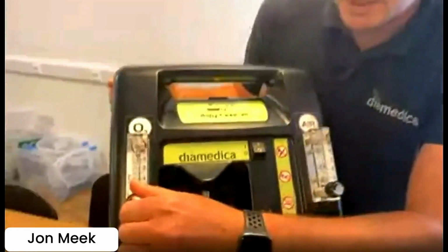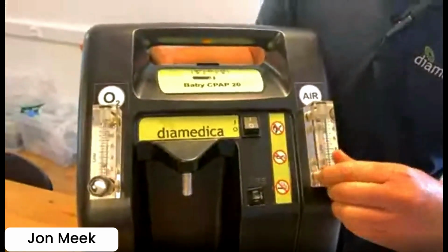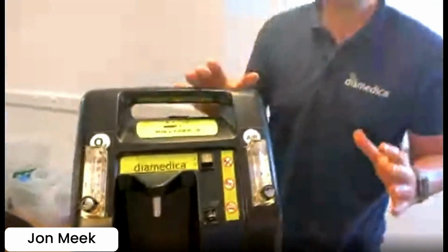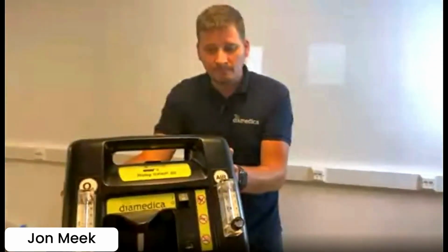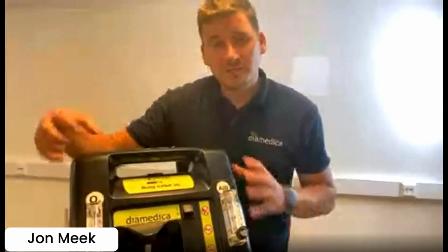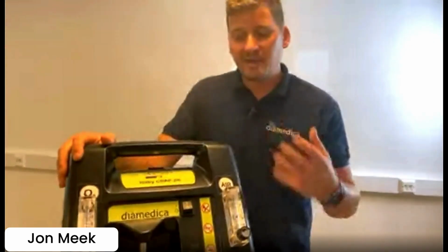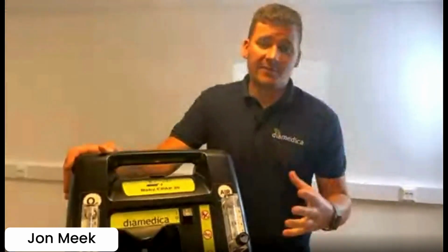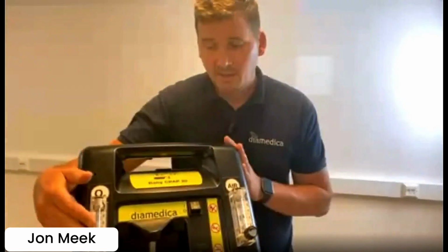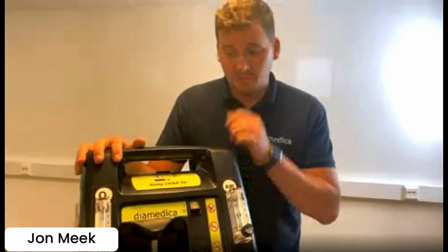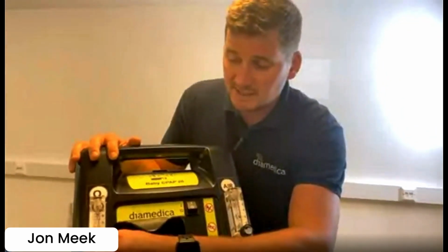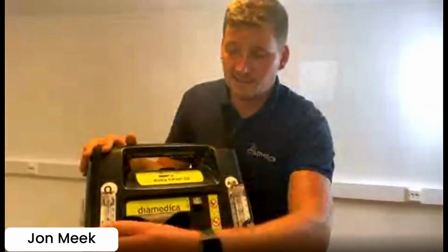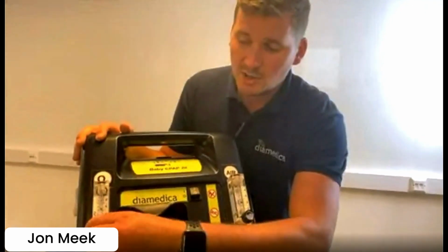So one check I'll do once this is warming up, we can check our flows reach the maximum and then set them back down, same as the air. It's really important because this generates now its own oxygen and air. It uses something called sieve beds to generate the oxygen. As it goes through the sieve beds, it absorbs all the carbon dioxide, nitrogen, everything in the atmosphere that's not required, apart from argon and allows 95% out. Because it's generating its own oxygen and absorbing, and everything is calculated through the sieve beds, the flow has a maximum rate. If you exceed this above the maximum, the machine will deteriorate a lot faster than it should do.